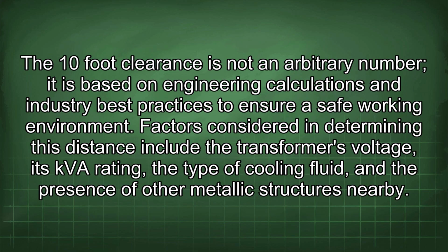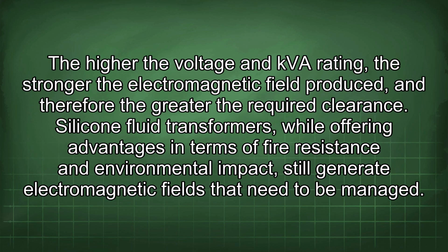The 10-foot clearance is not an arbitrary number, it is based on engineering calculations and industry best practices to ensure a safe working environment. Factors considered in determining this distance include the transformer's voltage, its kVA rating, the type of cooling fluid, and the presence of other metallic structures nearby. The higher the voltage and kVA rating, the stronger the electromagnetic field produced, and therefore the greater the required clearance. Silicone fluid transformers, while offering advantages in terms of fire resistance and environmental impact, still generate electromagnetic fields that need to be managed.